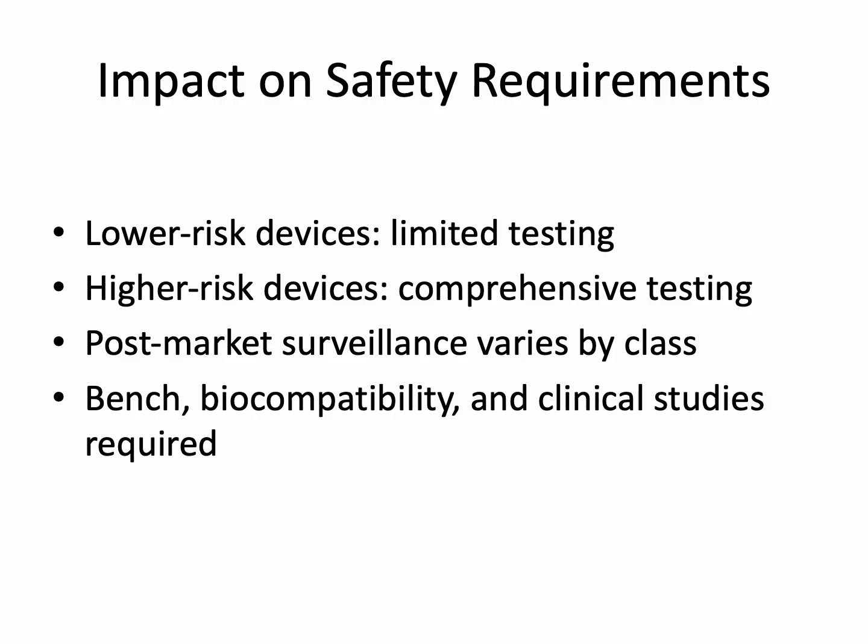Safety requirements are determined largely by device classification. Lower-risk devices, such as FDA Class 1 or EU Class 1, may require only bench testing, biocompatibility assessment, and limited clinical data. Higher-risk devices, including FDA Class 3 or EU Class 3, necessitate extensive safety testing, rigorous clinical trials, long-term follow-up studies, and robust post-market surveillance.